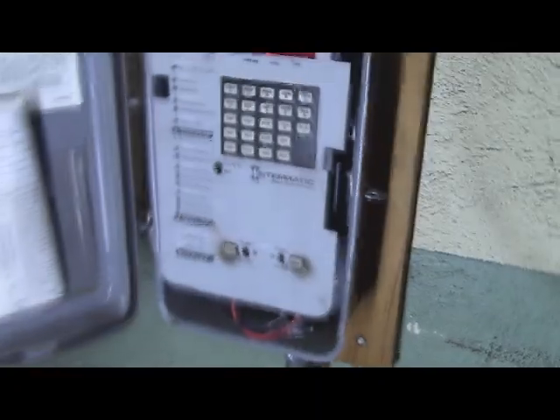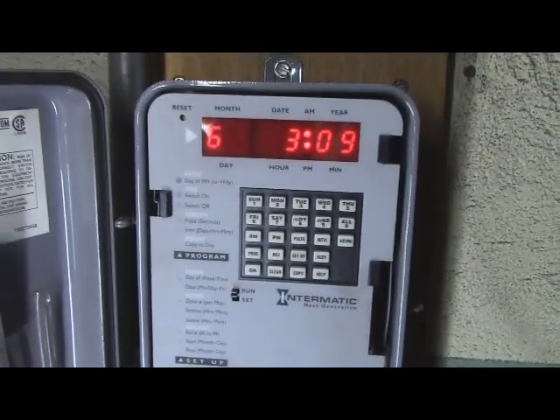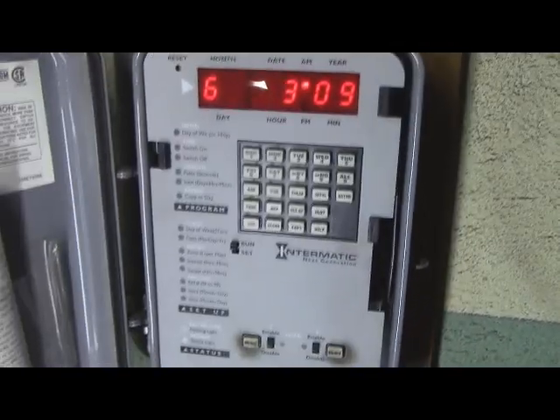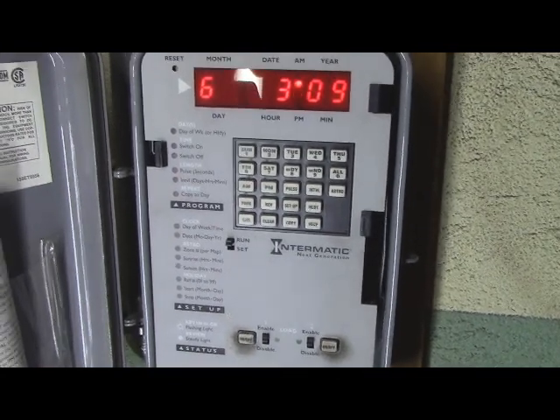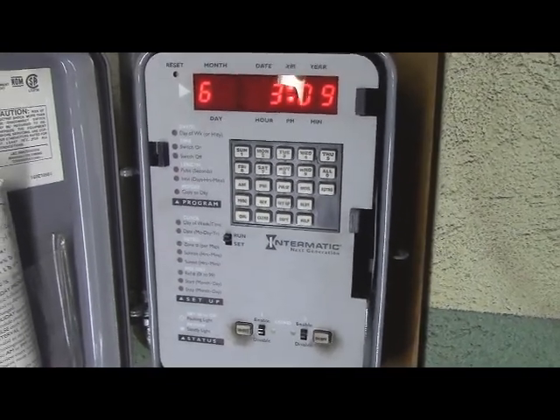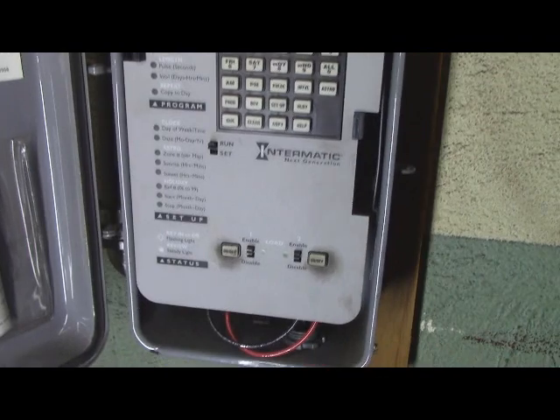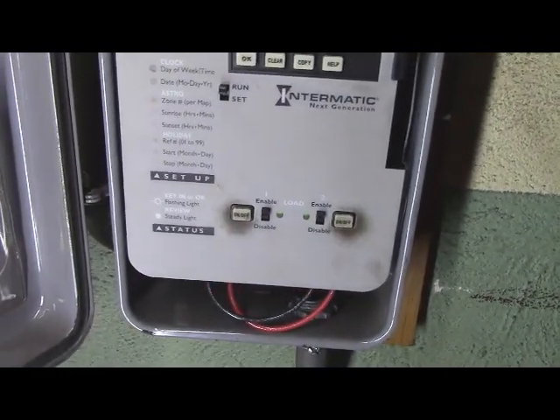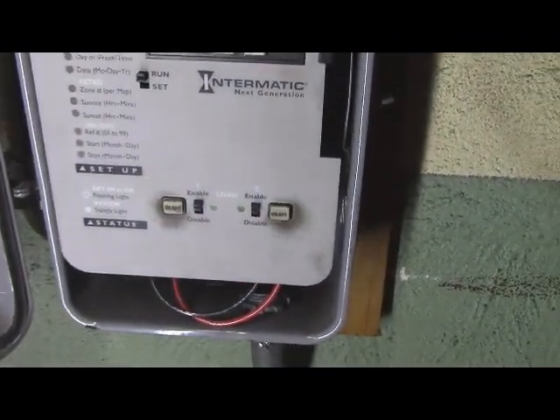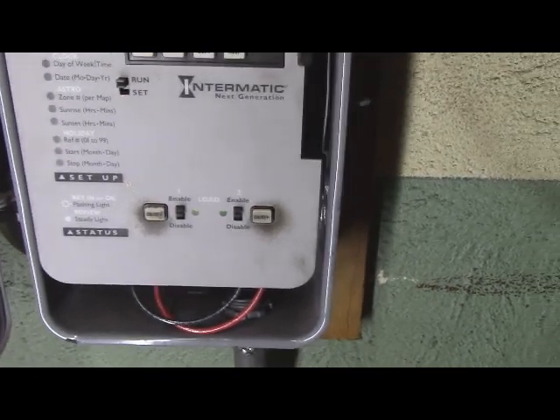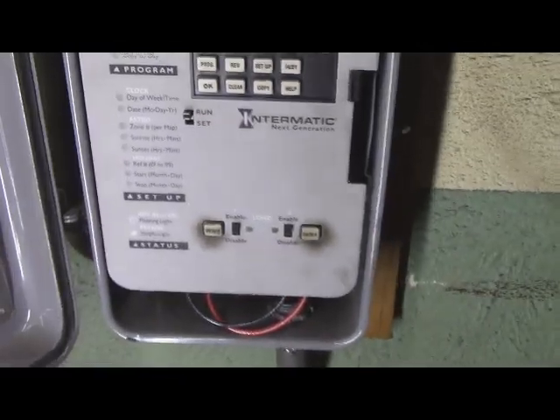And down here we have a very nice Intermatic 365-day timer. Very nice. A lot of capability. Intermittent stops and starts. Can adjust for sunset, sunrise in different geographical zones. Daylight saving. Really a lot of capability. 2 relays there. In this case, that left relay is controlling A and B compressor, and the second relay to the right controls the air dryer, air cooler.